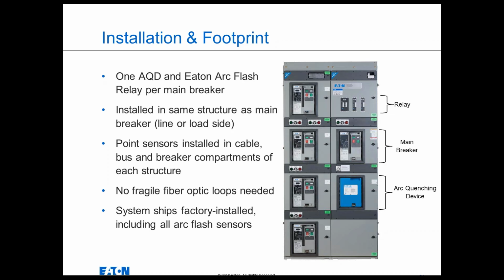The point sensors that detect the arc flash light, there are 3 installed in the cable compartment of every structure, 2 installed in the bus compartment of every structure, and 1 over the finger clusters of every draw-out device. And those are tested and validated locations. These aren't just our best guess. We did arc flash testing on multiple pieces of switchgear to validate where the sensors had to be to ensure that they would be placed properly to detect an arcing fault no matter where one initiated inside the switchgear.